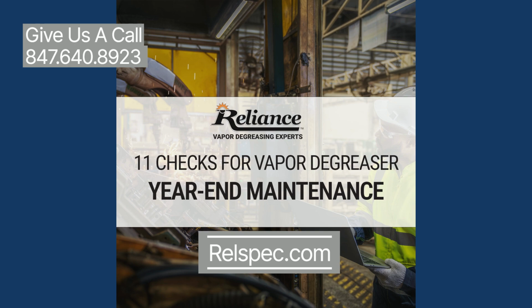Check 2. Inspect your electrical panel and other electrical components. First, inspect electrical panels for cleanliness and orderliness. There should not be dirt, debris, oil, or other foreign material within the electrical box. Next, check wires for nicks, breaks, or signs of overheating. Check terminal connections and wires at the terminal connections. Then check the contactors for corrosion or signs of overheating that might indicate an issue.